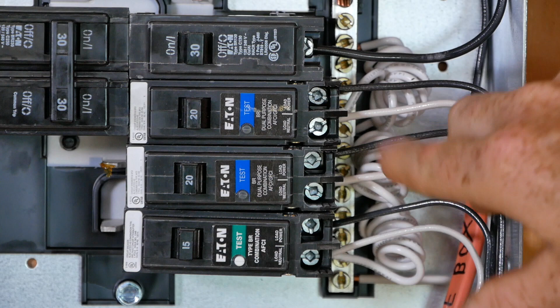Heading up into the inside of the box here, I like to label each of my wires inside the box as well. But if you're going to do this, you have to do it in a specific way, because code requires you to strip the sheathing off the cable inside the electrical box. So these bits of sheath you see here are pieces I labeled and then slid back over the hot wire only, and that's an okay thing to do. It's also nice because future you, who might not remember exactly what you did, has a quick reference when you open the box.